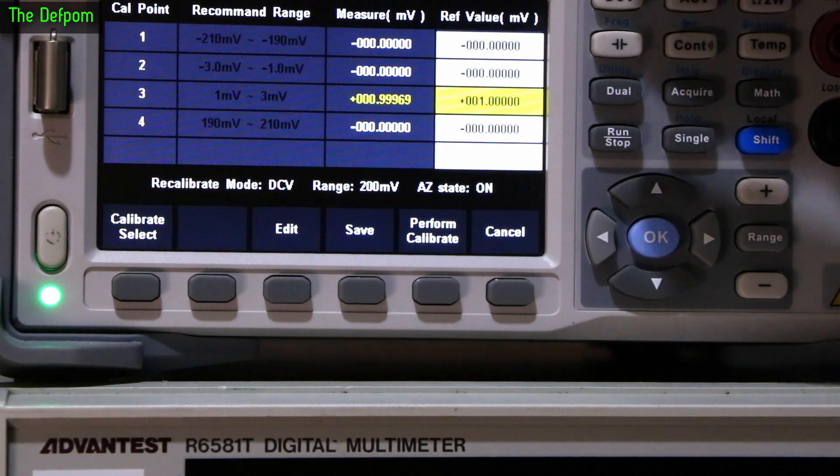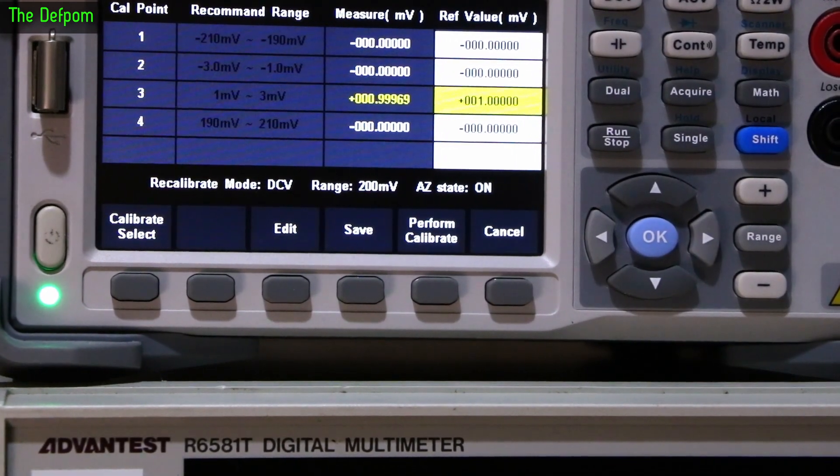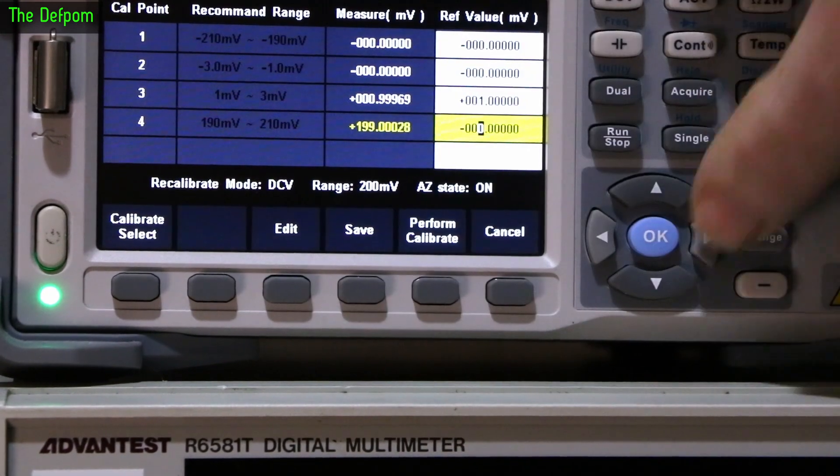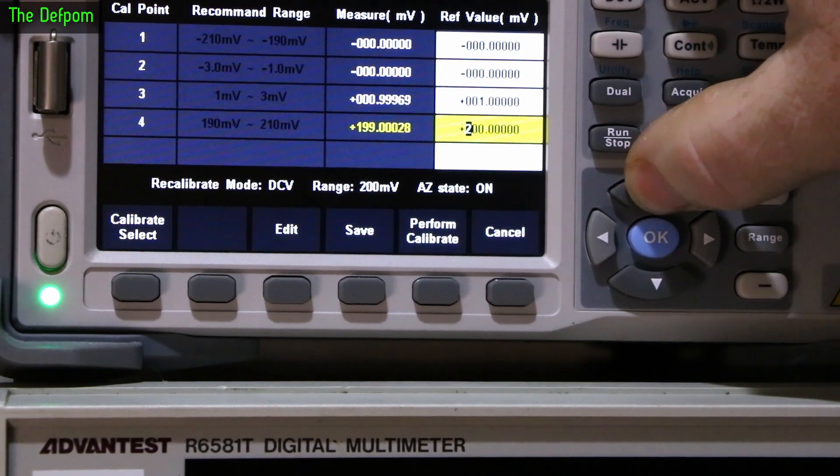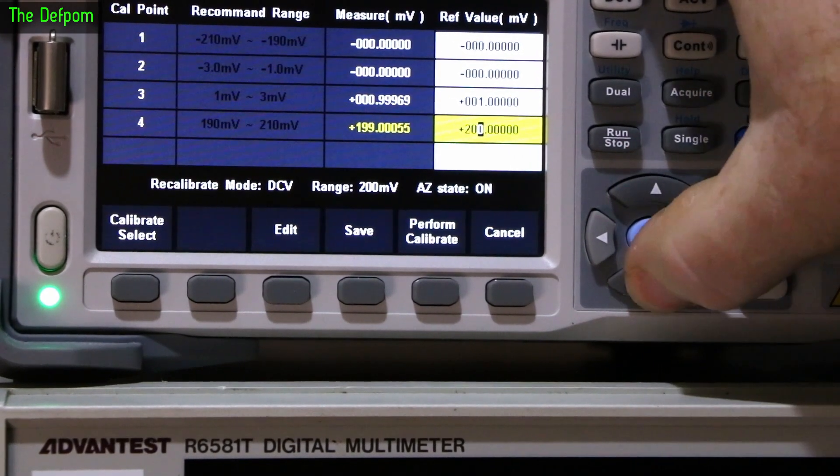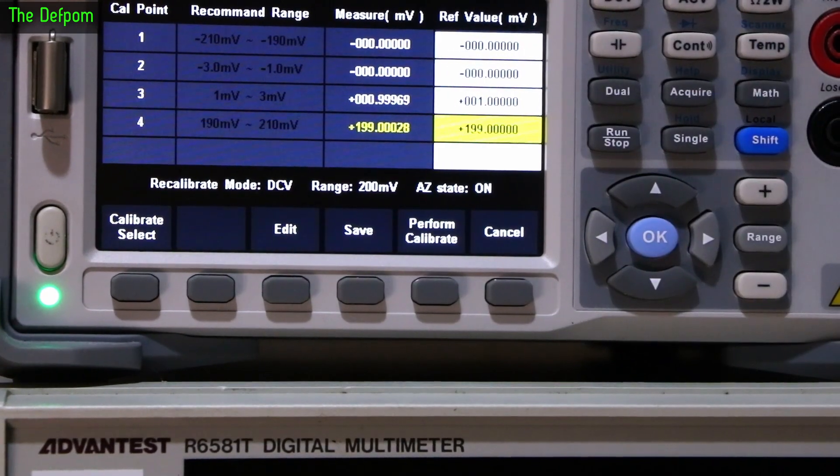I don't think sequence actually matters because you've got to submit them all at one time. Now we'll do the positive 199 millivolt. Calibrate, stabilize. Edit, I want to do positive 199 millivolt. That's exactly what's on the Advantest. Save that.